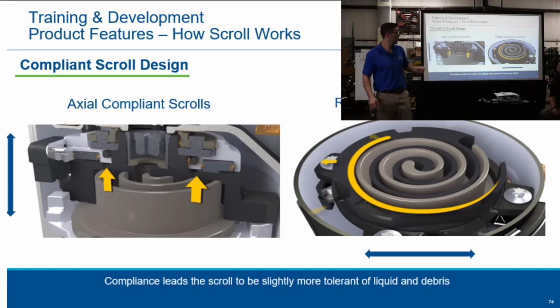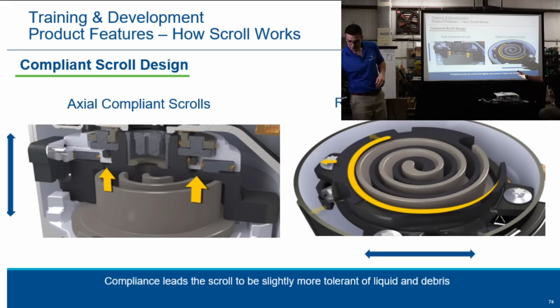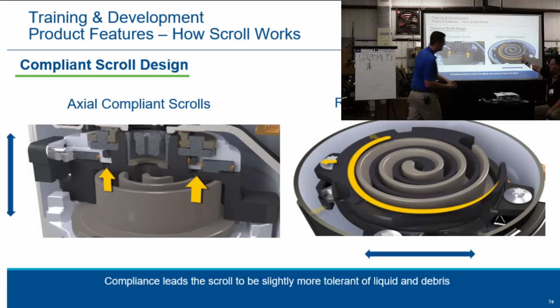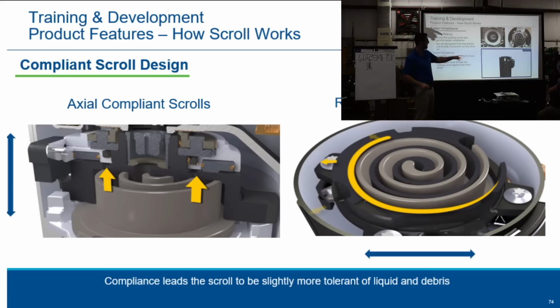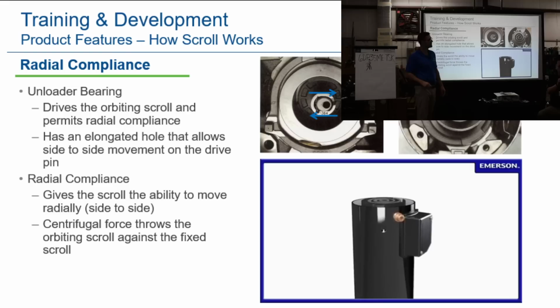Right. Okay. Go ahead. All I want to say is that's always brought up a lot. We don't want liquid refrigerant. It's not designed for that. In fact, what Trevor's talking about here, this radial compliance, that's what that does. When it senses a droplet of liquid refrigerant, or any kind of debris, it separates, kicks it out, and flashes that refrigerant off. Yeah, so it's designed to prevent it from coming in, is really what it's all about.